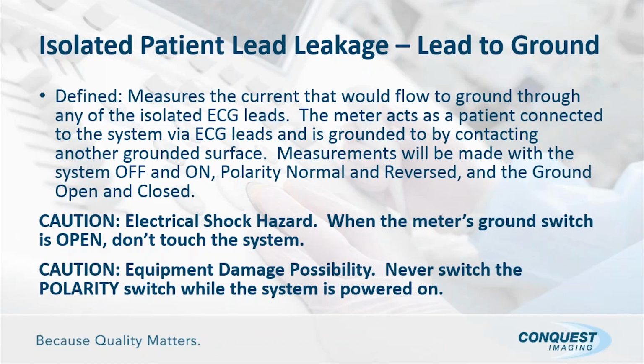Then we have to go to isolated patient lead leakage, or lead to ground. It depends again on what your specific meter or safety analyzer describes it as, patient lead leakage or lead to ground. So be careful, or at least understand what your safety analyzer's verbiage is. This measures the current that would flow to ground through any of the isolated ECG leads. And I know this sounds unusual, and I don't mean to insult anybody, but at this point, if you don't have ECGs, you don't conduct these tests. It's clear that way, but I actually have had calls saying, how are we supposed to meet the requirements of this when I don't have an ECG?